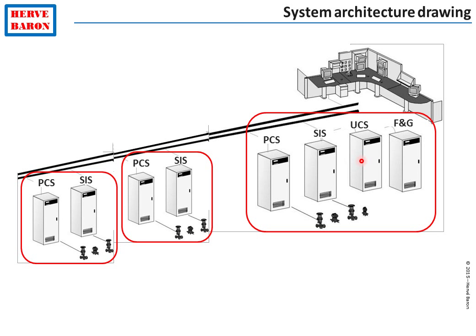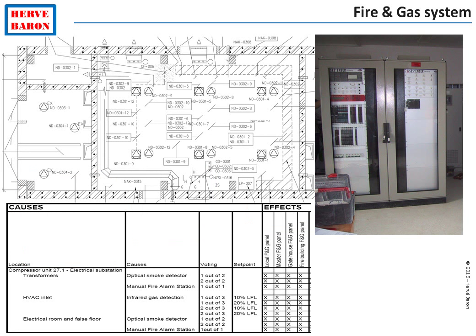The fourth and last type of cabinet found in instrumentation equipment rooms is the fire and gas cabinet. So there are four types of cabinets: process control system, safety instrumented system, equipment unit control systems, and fire and gas cabinets. The fire and gas system is defined by safety, which specifies the number and location of detectors and their logic of operation on the cause-and-effect chart. The system is then purchased and programmed according to these two documents.